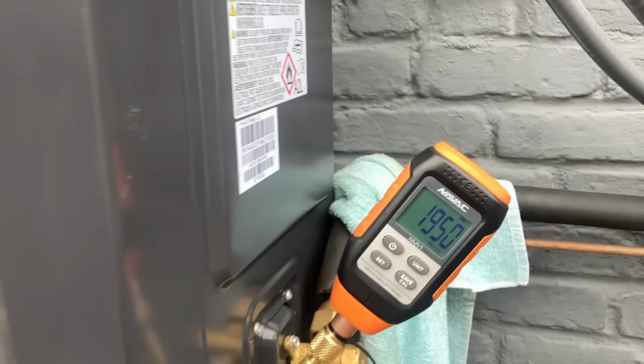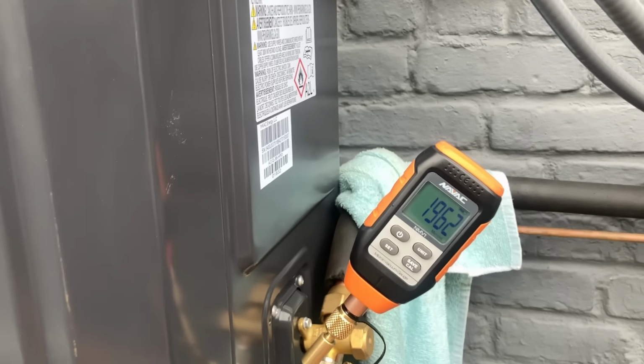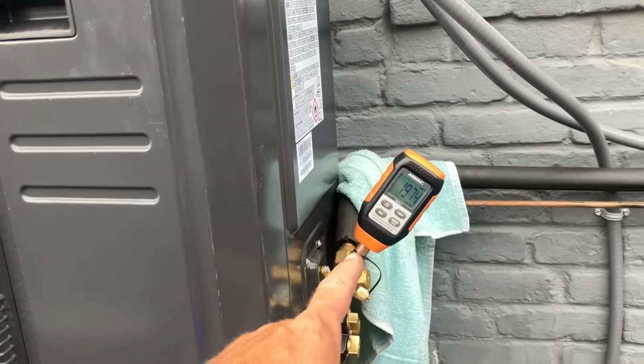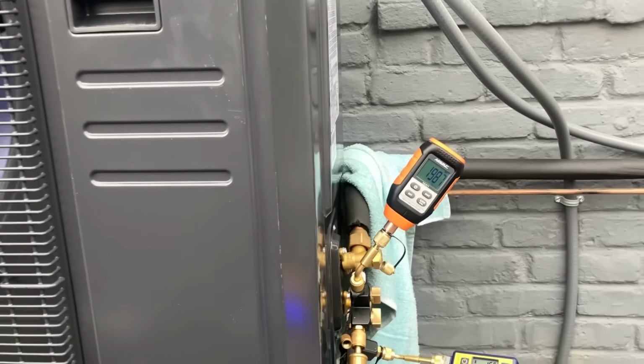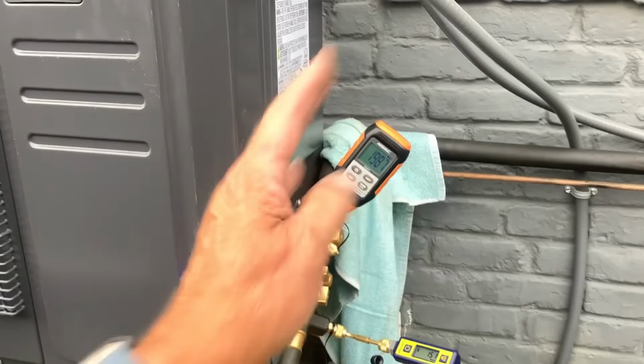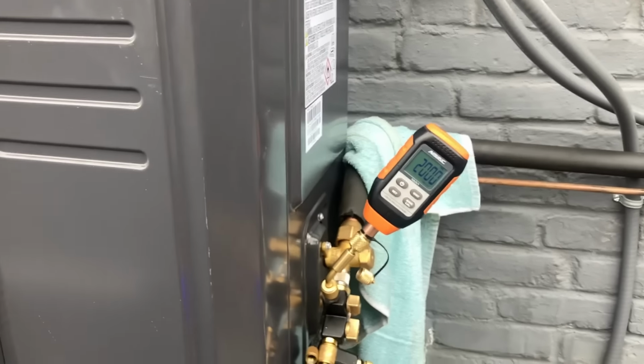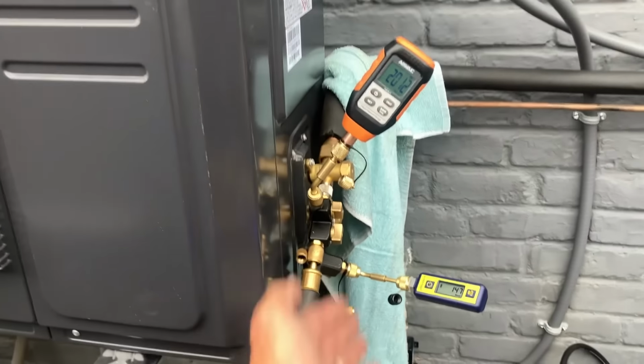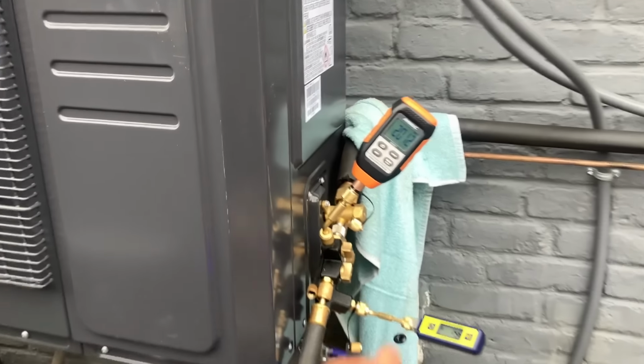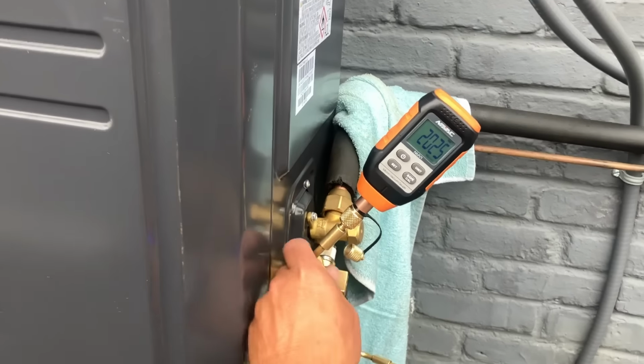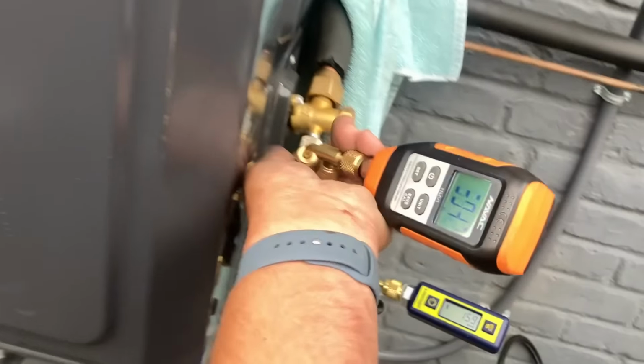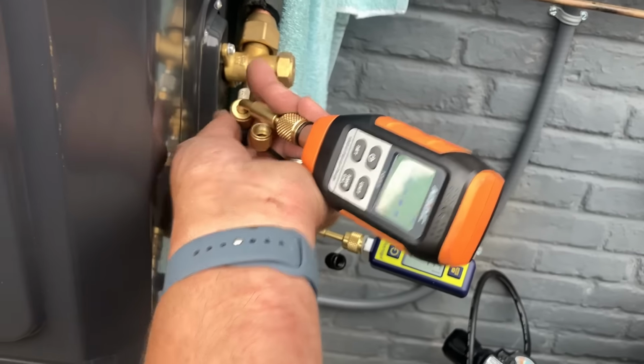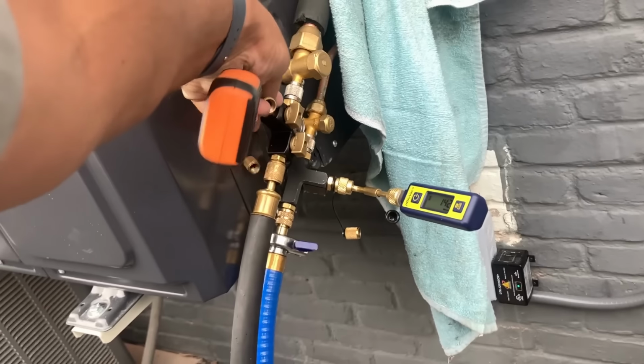Open up the valve there. This one, I don't know. I don't trust this thing with a 10-foot pole. Seriously, I do not trust the Navac micron gauge. I do not trust it at all. Why do I still keep using it? I don't know. Look, it's still going up, and the vacuum pump is connected to it. All right, let's see what happens if I take it off. Oh, that worked out real quick. Right? That went back to 0 real quick.